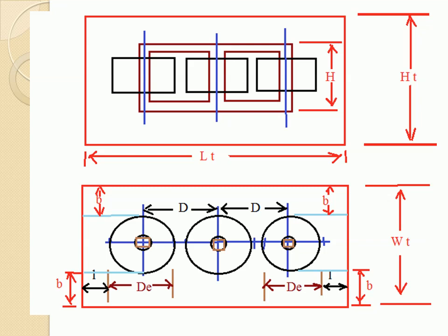Small l is the length of the clearance between the HV winding and the surface. Small b is the clearance between the HV winding and the surface along the widthwise direction. Small h is not available here. For small h, you can assume all three distances: base, minimum oil level over the assembly, and tap changing requirements.